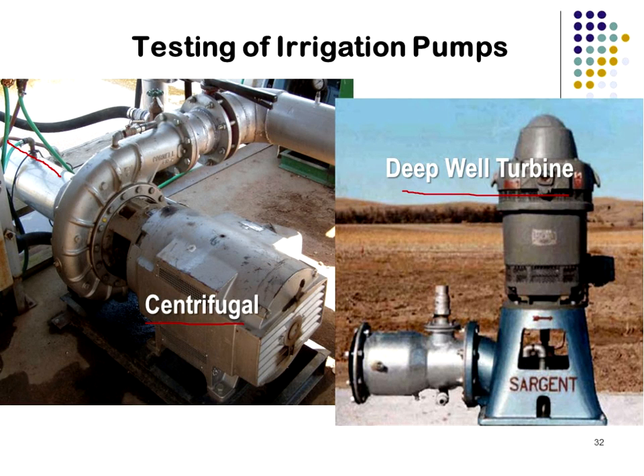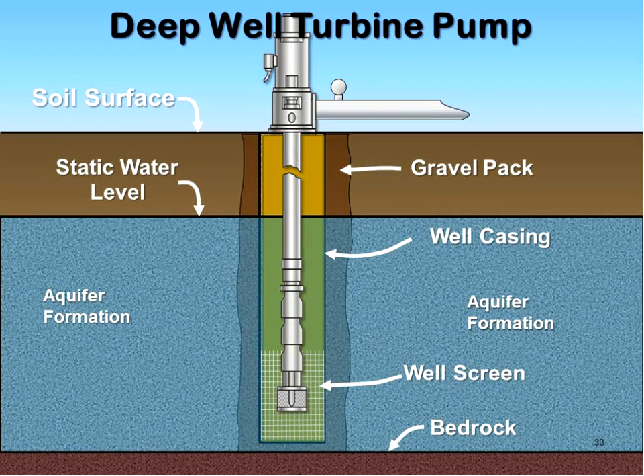And the efficiency is lower on these than it would be for a deep well turbine pump, where part of the pump is actually in the water. So this is what you're seeing. This is the motor. Sometimes they're a right angle drive, and this would be the outlet for the pump, and then there's a shaft that extends down into the well. So that's what we're trying to show here.